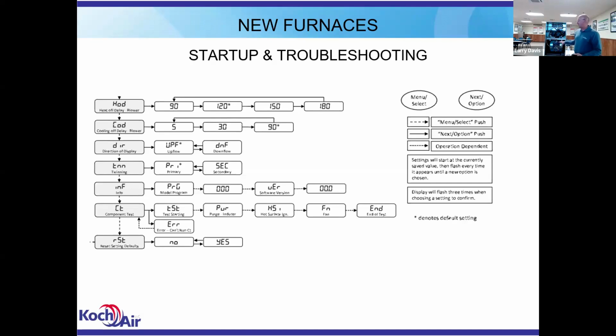And we have to tell the secondary furnace that it's a secondary furnace. Which one's a secondary furnace in a twinning set? It's the one that doesn't have the thermostat wires connected to it. So default in the board is primary. Primary board says, I'm the main board in control. I'm looking for thermostat input. You put a twin furnace there. If you don't tell it it's the secondary, it's going to look for a thermostat input and it's not going to run. Okay, so that's what the twinning does.